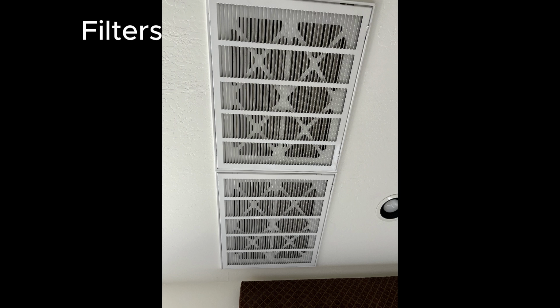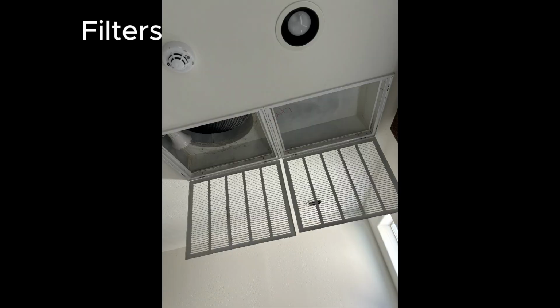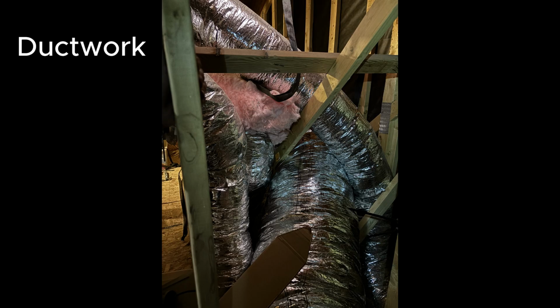And if you don't change your filter, it can significantly impact the efficiency of your system, and it can really do some damage. It can even frost up your evaporator coil, because if air can't get from inside the home across the evaporator coil, then the coil can't absorb heat, so it just stays perpetually cold, and then it keeps getting colder and colder below 32 degrees Fahrenheit, to the point where when water condenses on it, which is normal, it actually creates ice and freezes, which is a very common thing for service techs to see. So filters are important. I get asked about that a lot, and they can really impact your system if you don't change them out regularly.